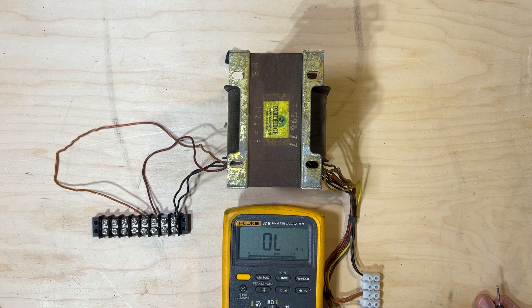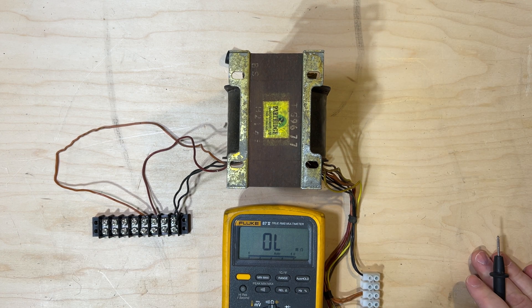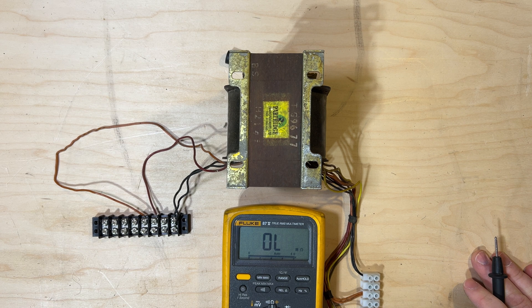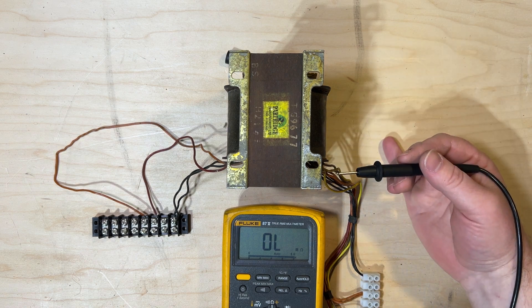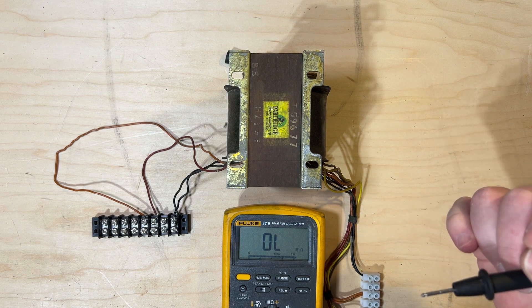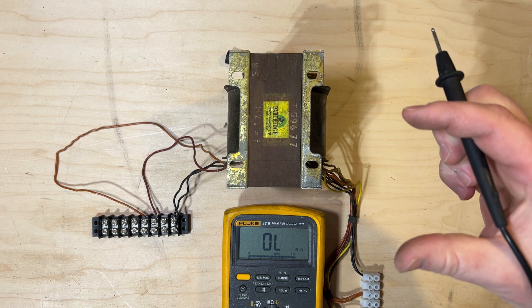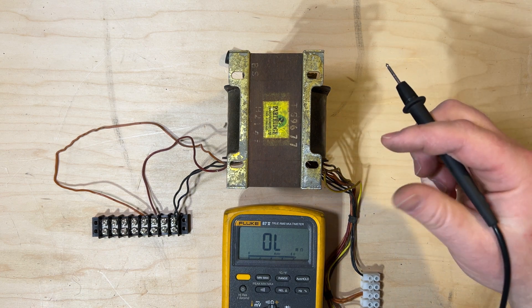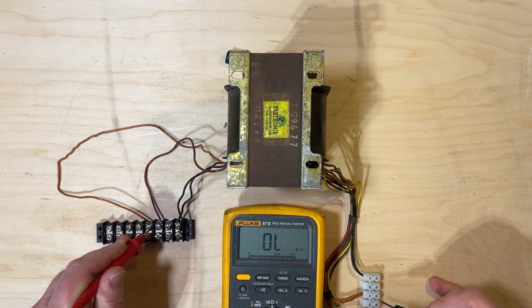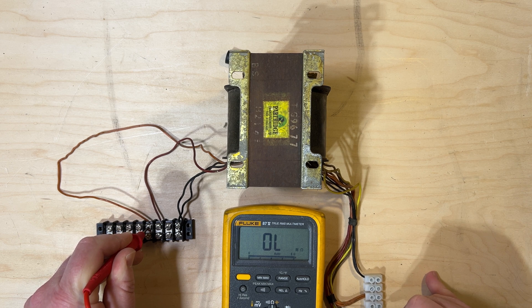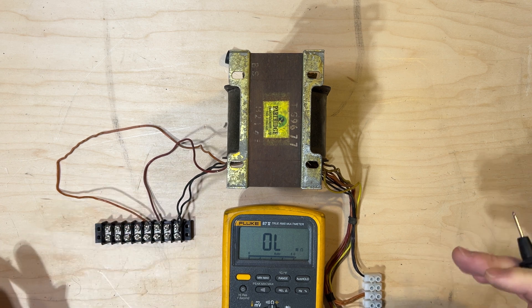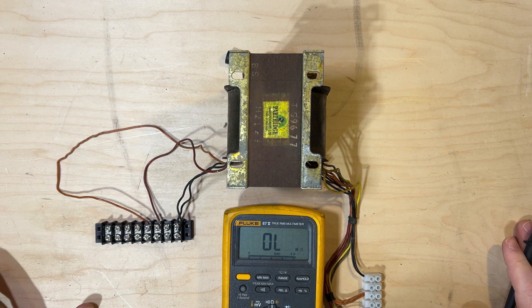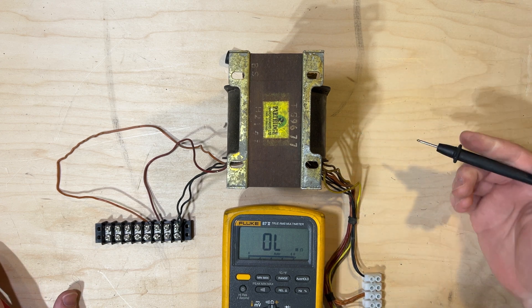So, that's a good test. Now, really, with a resistance check on something like this, it's not an ideal test. The way that transformers work and the way that they fail, they have stacks of coils. And those coils of wire have very, very thin insulation on them that can melt. And then, suddenly, your stack of coils that's this tall is instead this tall. And, unfortunately, those issues could be there and we wouldn't measure them. You may measure them from a resistance test like this. But they also may only show up when under power, when under a higher voltage or an operating voltage that's typical to the transformer. Because the insulation won't break down until there's that potential across it.